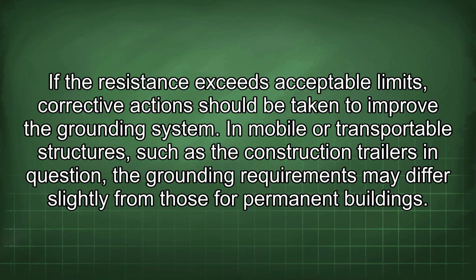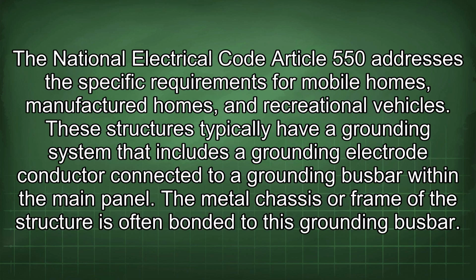In mobile or transportable structures, such as the construction trailers in question, the grounding requirements may differ slightly from those for permanent buildings. The National Electrical Code Article 550 addresses the specific requirements for mobile homes, manufactured homes, and recreational vehicles. These structures typically have a grounding system that includes a grounding electrode conductor connected to a grounding busbar within the main panel. The metal chassis or frame of the structure is often bonded to this grounding busbar.